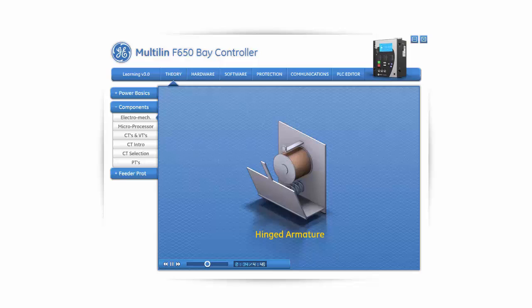As the hinged armature relays operate, the length of the magnetic air gap changes, resulting in a slightly greater force required to just pick up the armature than the amount of force that is required to release the armature. This translates into a difference in the amount of measured quantities for pickup and dropout, which is a slight impairment for this style of relay. This shortcoming also applies to the plunger style of construction, but to a lesser extent.